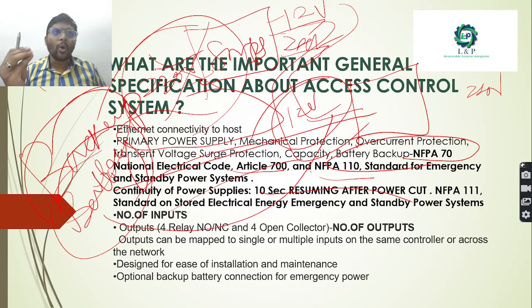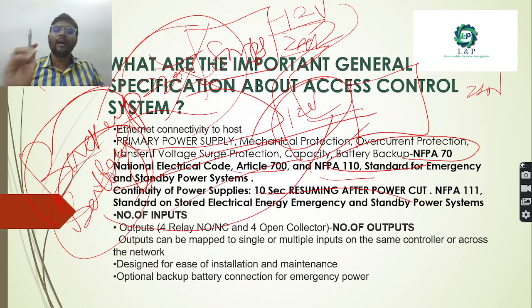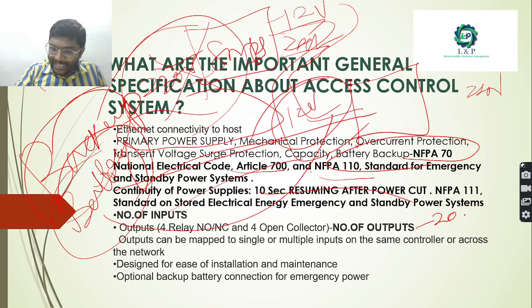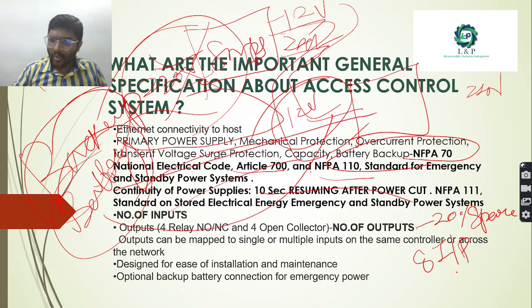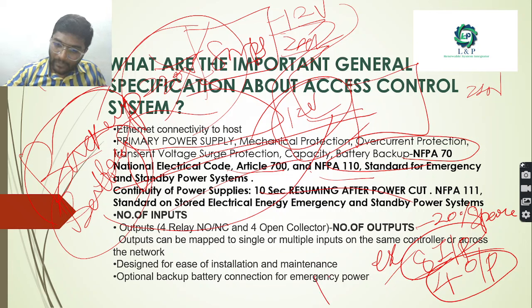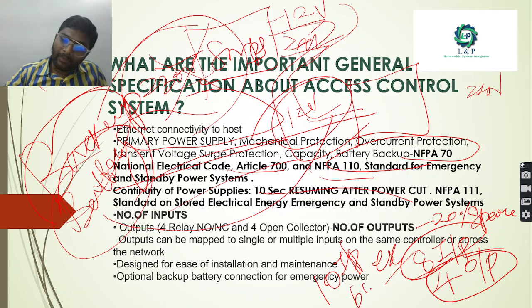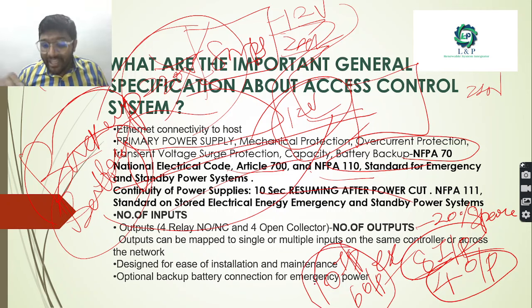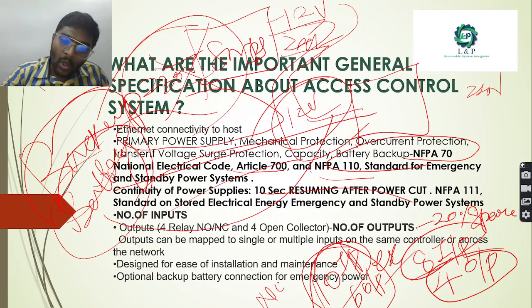When planning a controller, always consider 20% spare capacity. For example, if you want to control 8 inputs and 4 outputs, it is better to choose a controller with 10 inputs and 6 outputs. This spare capacity accounts for any additional relay, normally open (NO), or normally closed (NC) contact requirements that may arise.